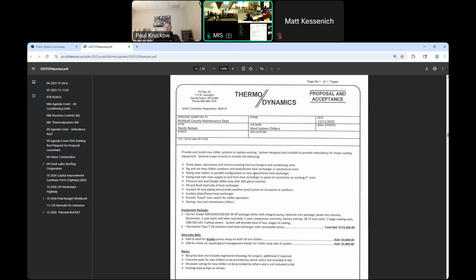Going through a couple of notes here. The biggest thing I see is the refrigerant side of it. When I looked at the project, my goal was to get the refrigerant out of the building. And this does that. It's a stainless plate frame heat exchanger inside with a glycol loop running out to 2 chillers. Each chiller has their own pump. They talk to each other through communication.